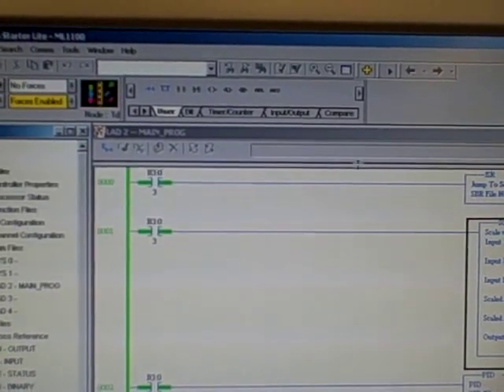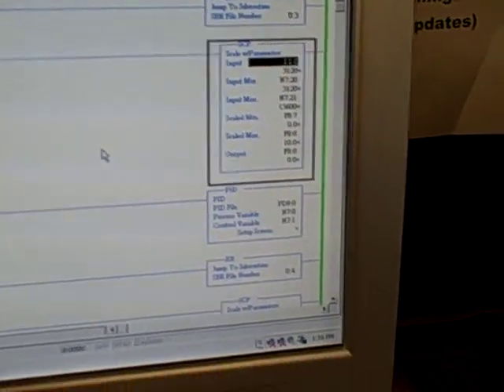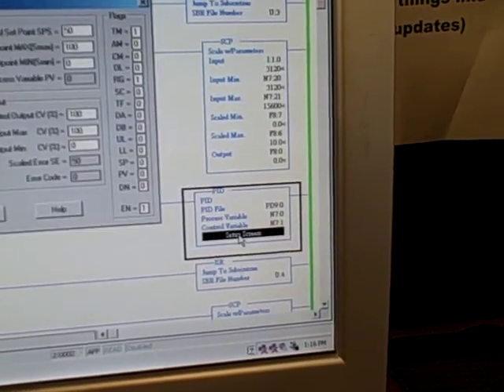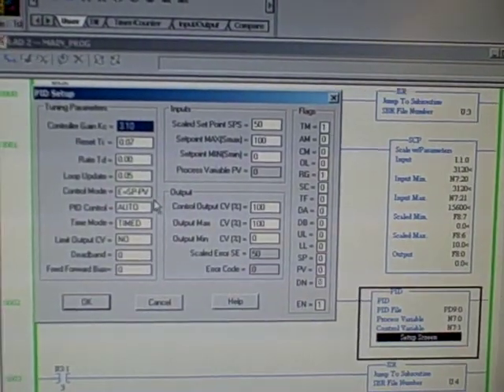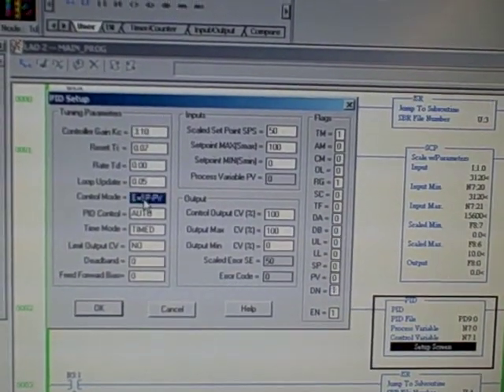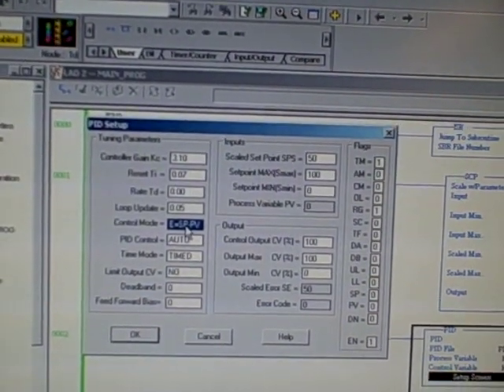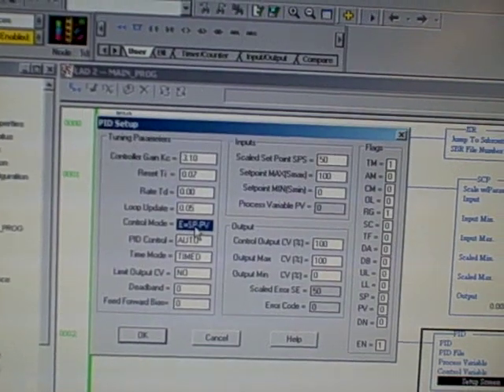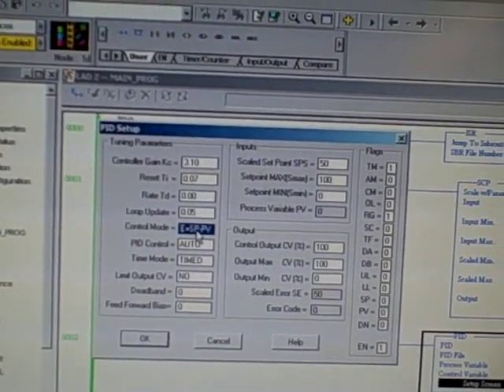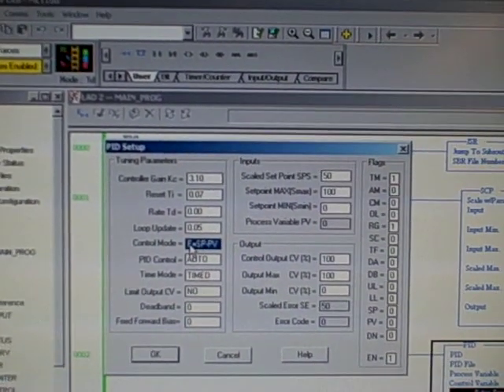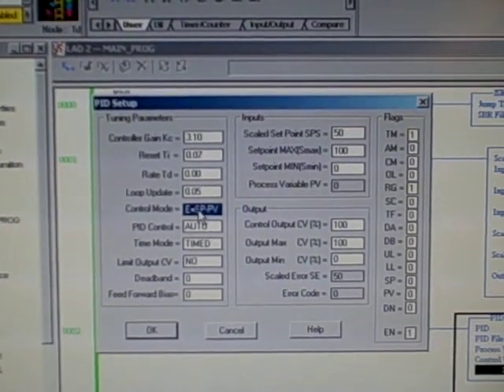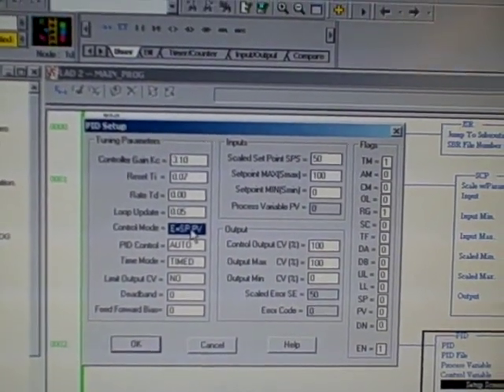Now, another thing you may need to change when setting up your loop for your process is some of the parameters inside the PID instructions. We'll click on the setup screen here, and one of those parameters you'll be interested in is the control mode. This is going to be controlling whether the PID instruction does direct or reverse action. Right now, the way it is, error equals setpoint minus PV, this is configured for reverse action.